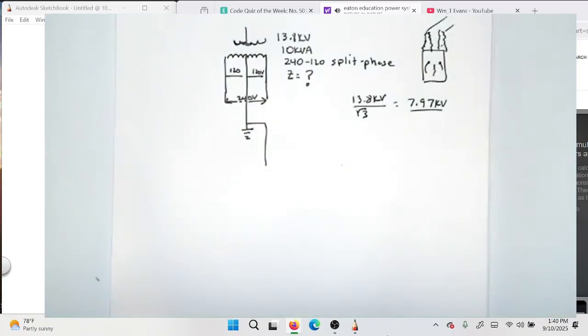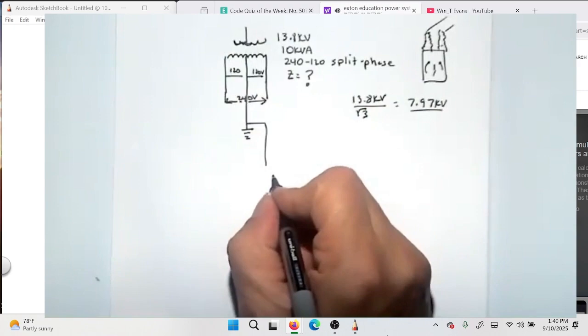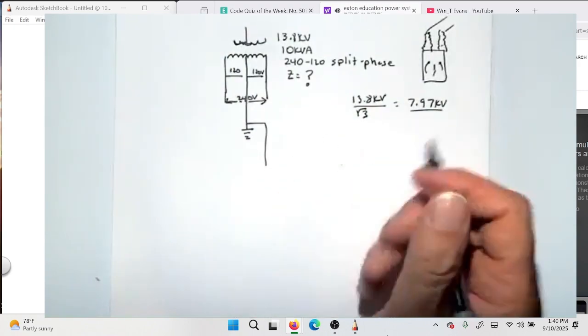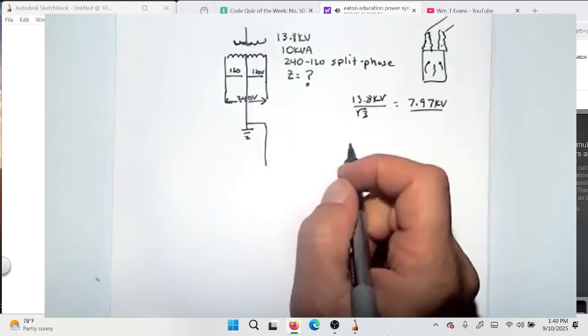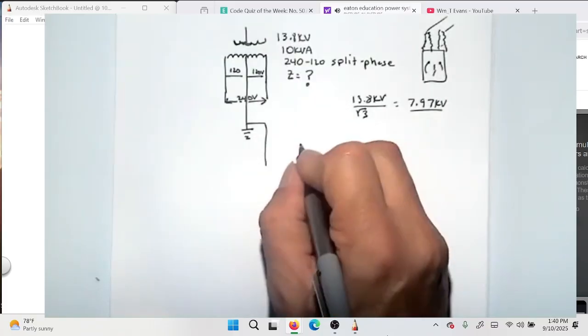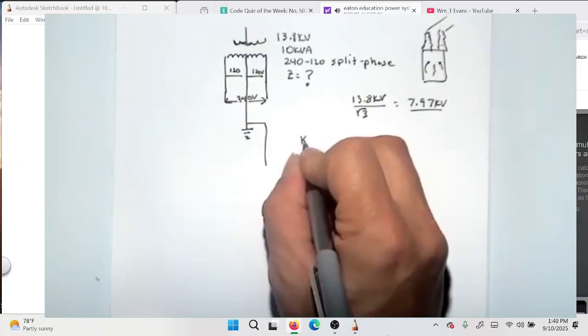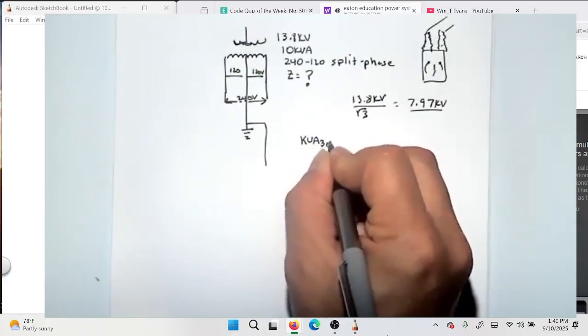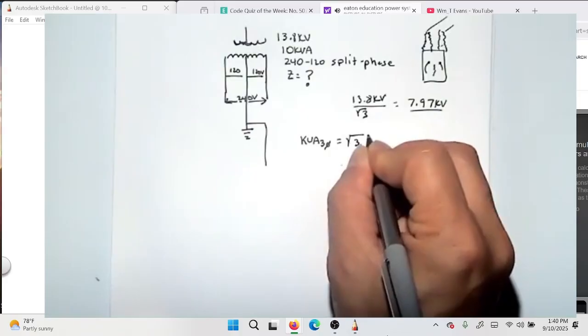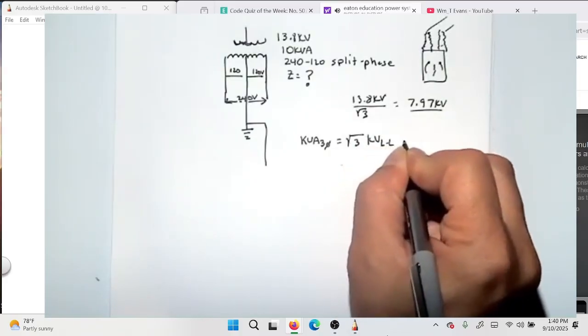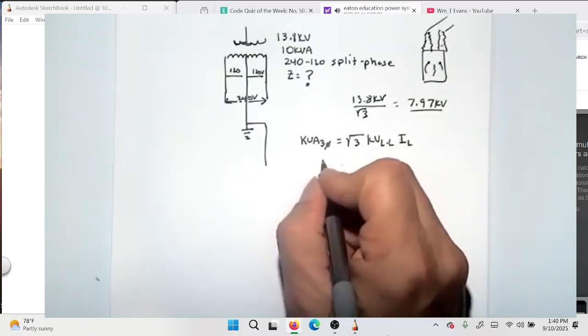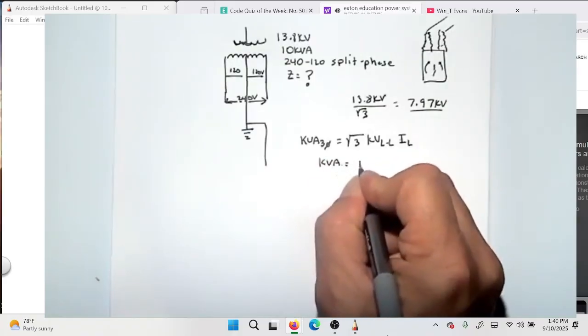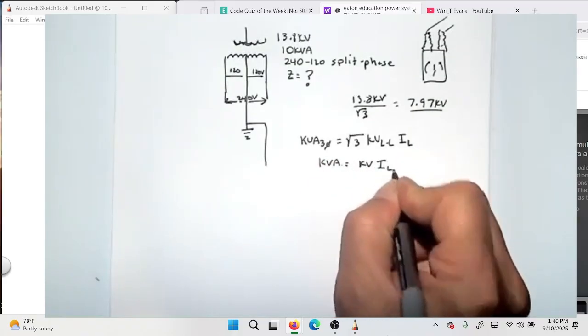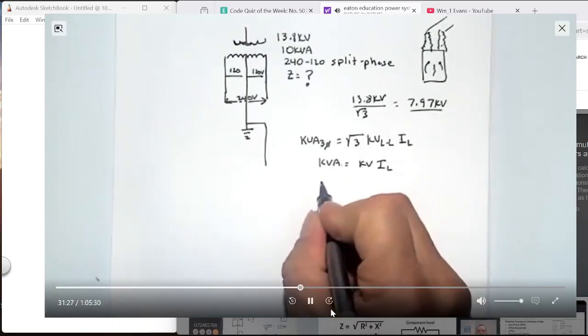So what are we going to calculate? The breaker that's in your home typically is a 2-pole breaker that's connected on that 240 volt line. So we're going to calculate based on the 240 volt. So instead of using kVA 3-phase is equal to square root of 3 times kV line to line times I line, we're just going to say kVA equals kV times current. In this case, we know the kVA. Got that? So this is single phase.